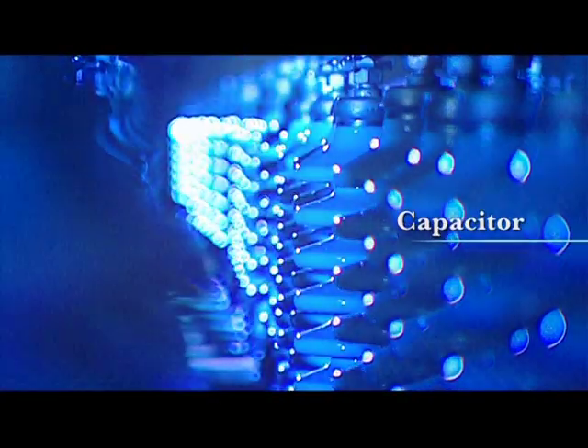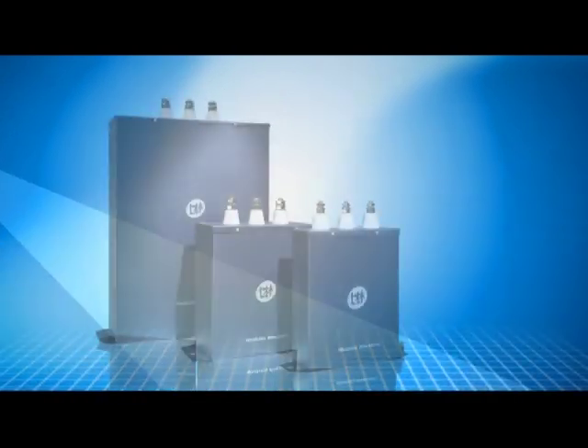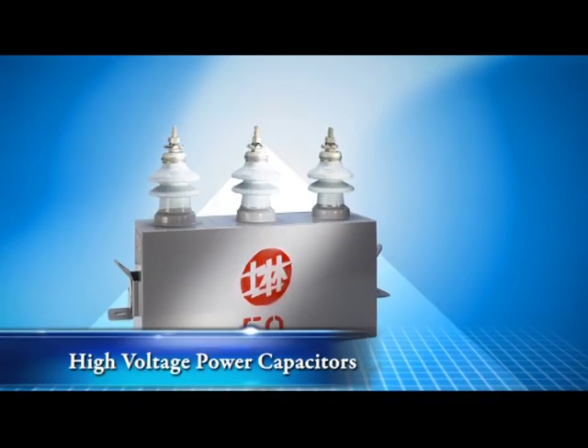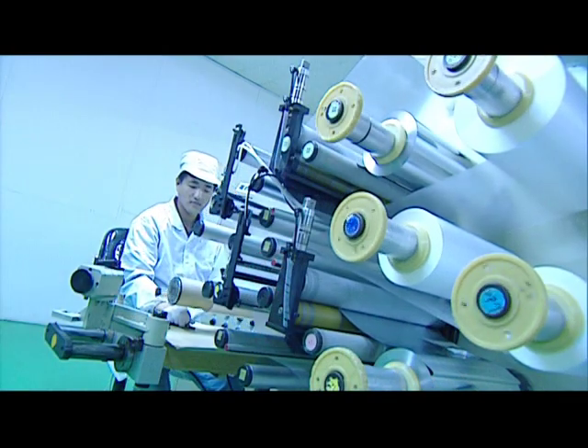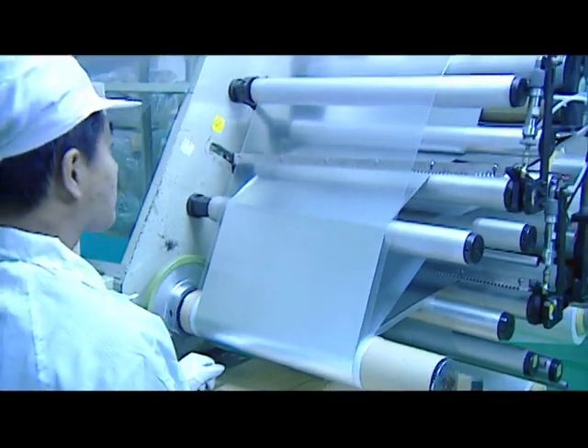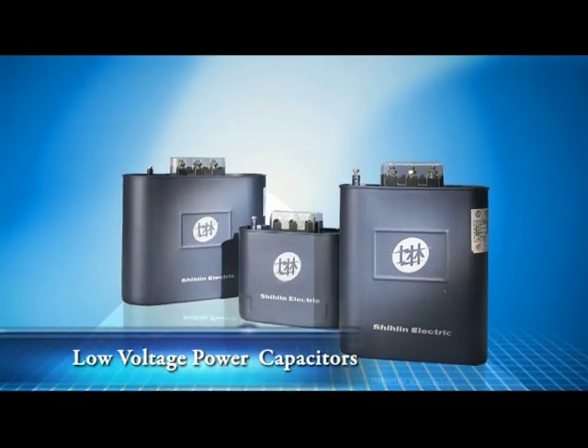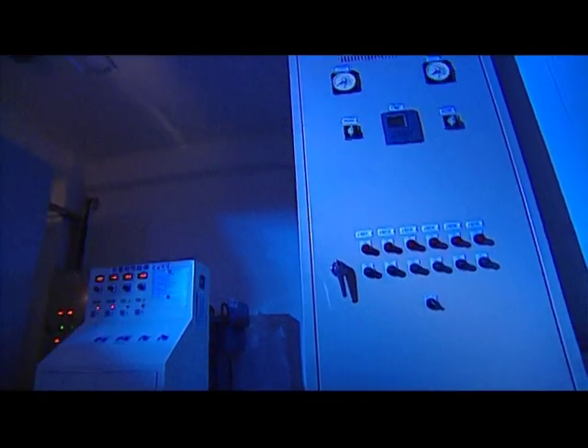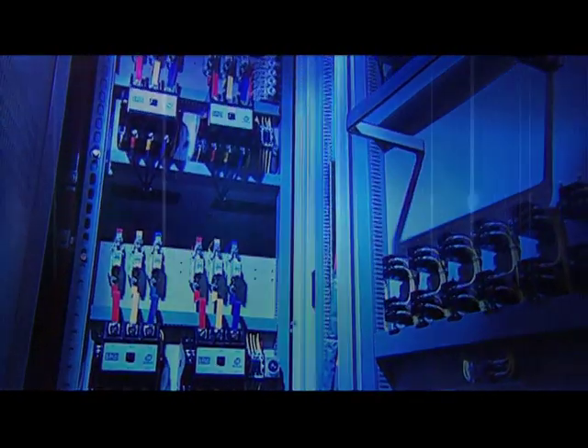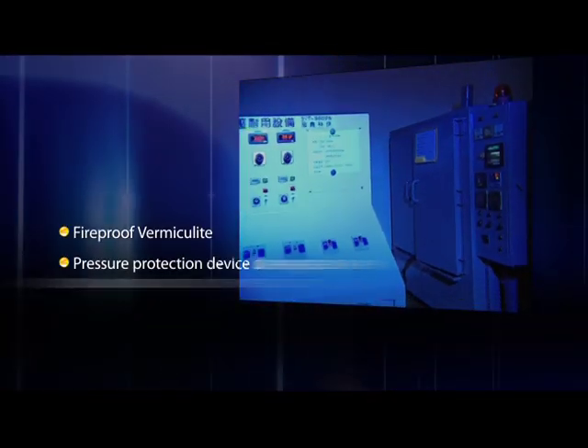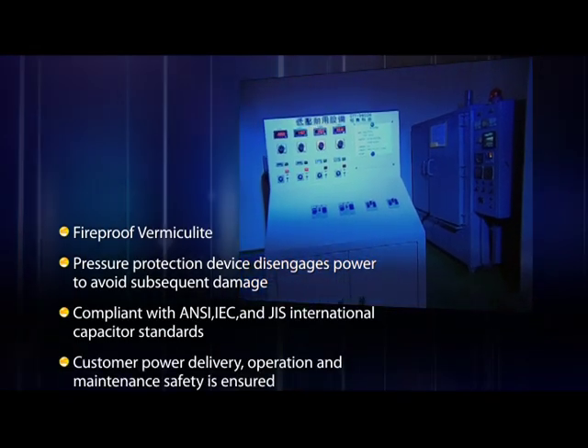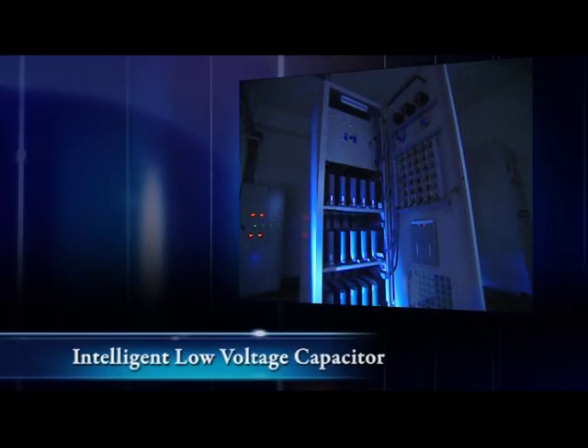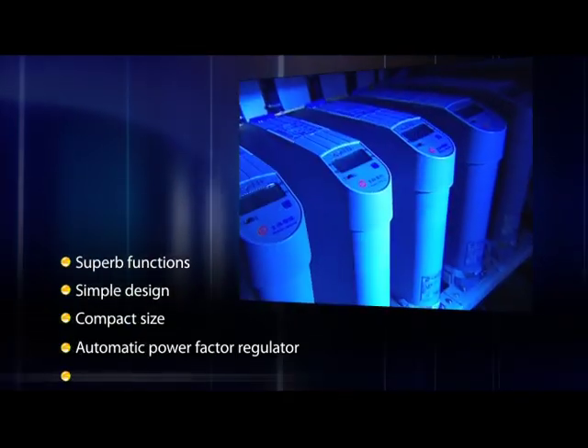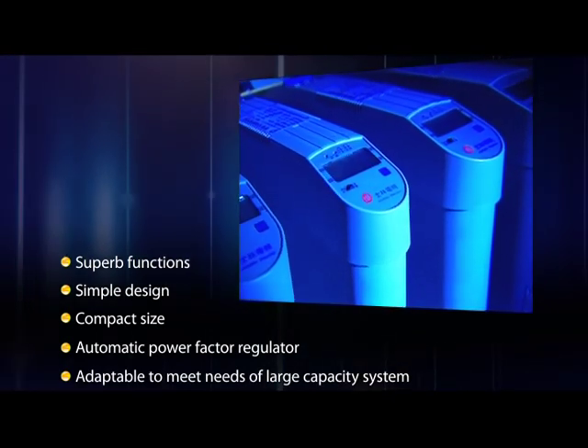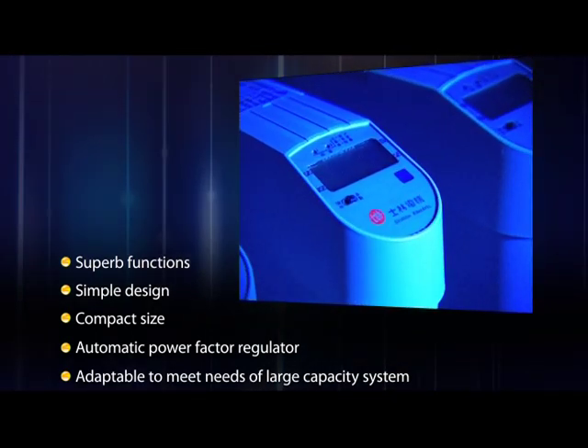SHIHLIN Electric has developed high voltage, low voltage, and intelligent low voltage capacitor products to help customers raise power system capacity, reduce power loss, and cut customer costs. Low voltage capacitors are encased within high tension steel casing. Should a severe malfunction cause a sudden and massive release of energy, fireproof vermiculite will absorb the breakdown and discharged heat to ensure the safety of capacitors remains uncompromised. Equipped with pressure protection, inline temperature sensors, and LCD display to show real-time data on power streams.